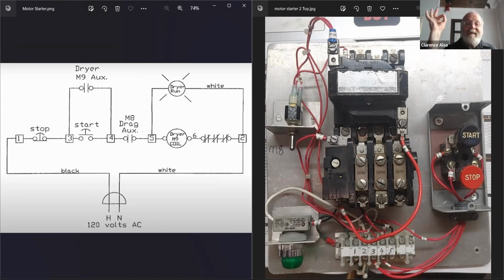You're going to put your probe down in there with your fingers there at the end of your probe, and then you're going to be pushing the button. And if I tell you that when you push the button it said 0 volts, what does that tell you? That your coil or your auxiliary is bad.